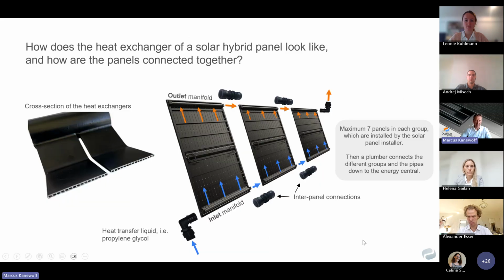But firstly, to make it less abstract, just to see the backside: a heat exchanger, it's a box channel, micro channel. And here is a fluid, it's glycol, circulating from panel to panel, but also through these micro channels. So the production is made in one panel, and then they are in parallel hydraulically. But electrical, it's just like PV. So PV installers take care of the mounting of the rows or groups with this interpanel connection for the hydraulic circuit. And then from here, where you have a thread in the inlet and outlet, it's a plumber's work or heat pump installer work. So it's very clear, and disciplines don't have to wait for each other.